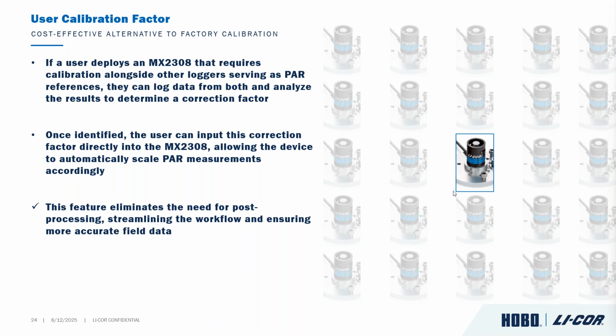So they deploy them in the same environment, do some level of analysis, and come up with a correction factor, because of the nature of electronics over time, or wear and tear, sensors may drift a little bit. So generally what our users would do, once they have that calibration factor, then they'll deploy their old units, and once they access that data afterwards, they do some data post-processing and apply that factor.